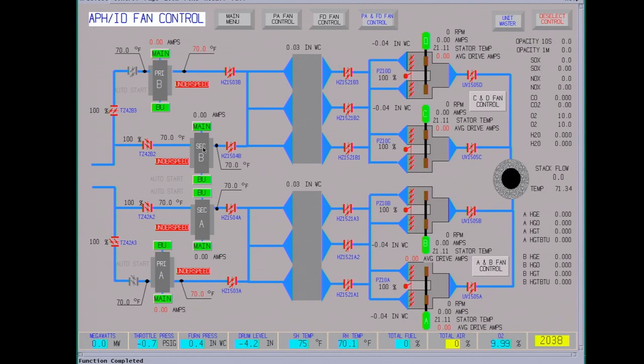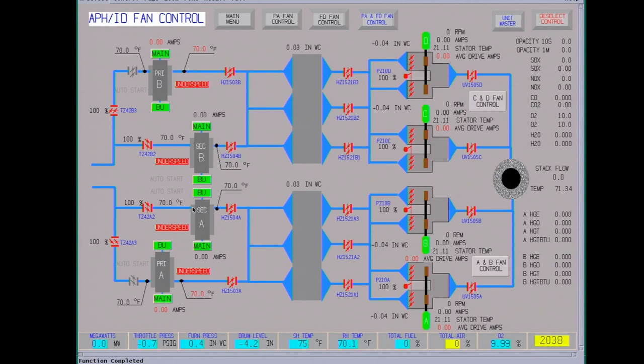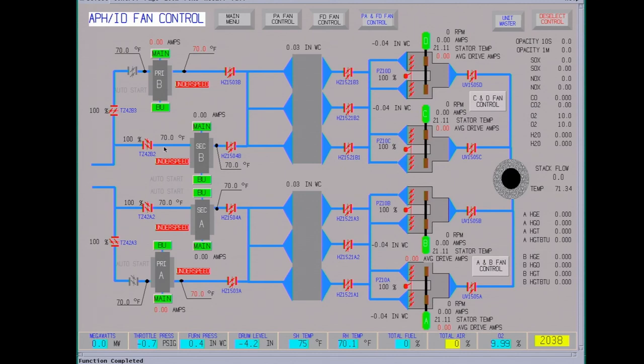They're a regenerative type heater. The secondaries are about 30 feet across, primaries are a little smaller. You have the flue gas comes through one side of the wheel and the other side is your air going into the fans, from the fans to the boiler. So basically transfers heat from your flue gas back into the boiler, helps the plant efficiency quite a lot.